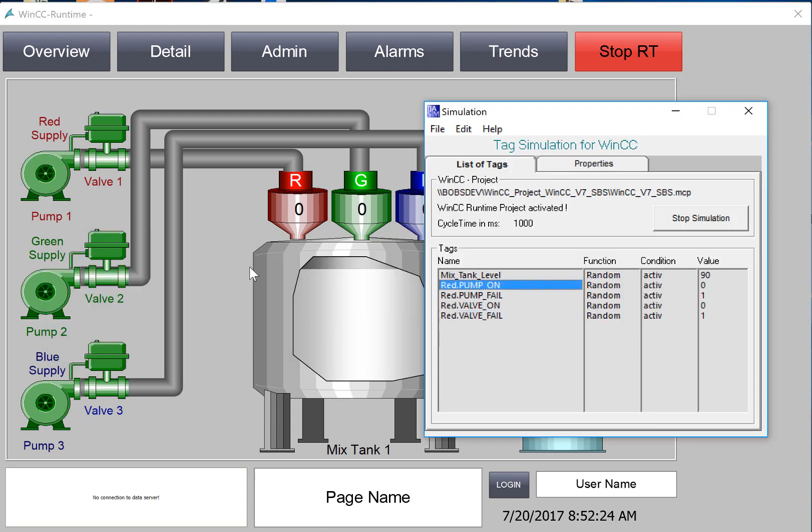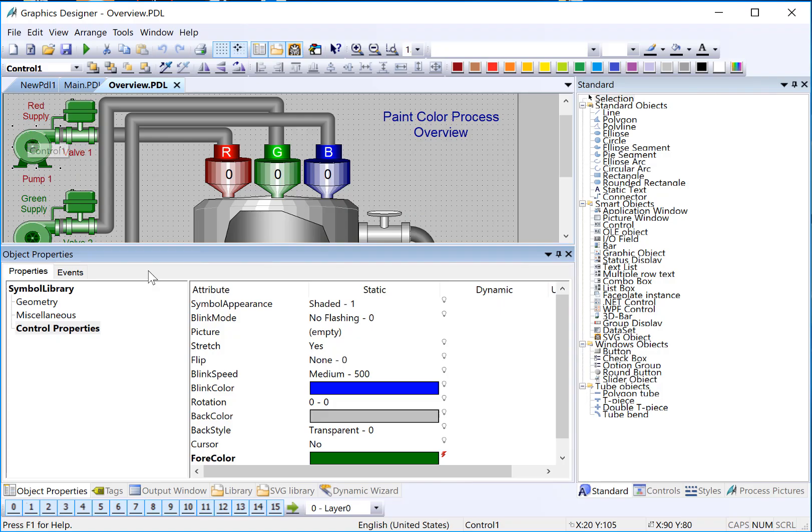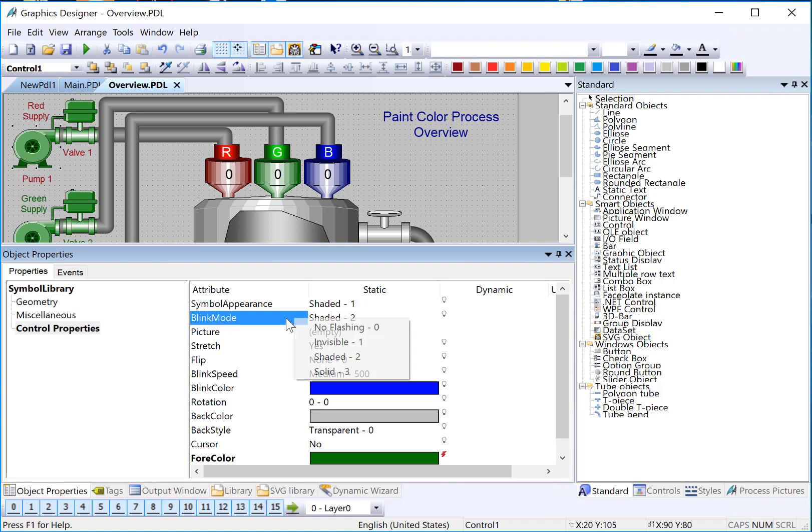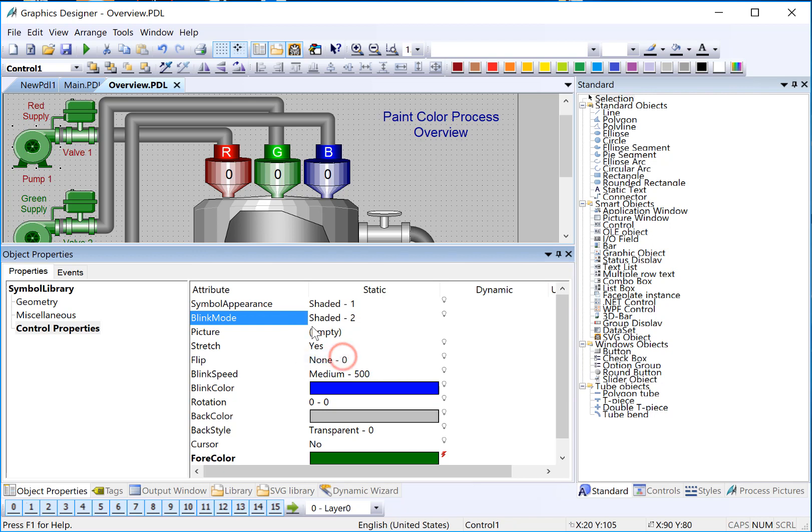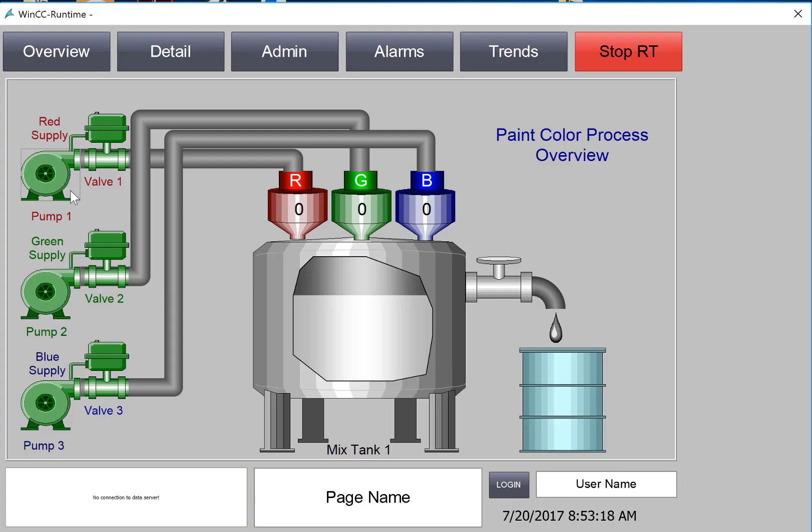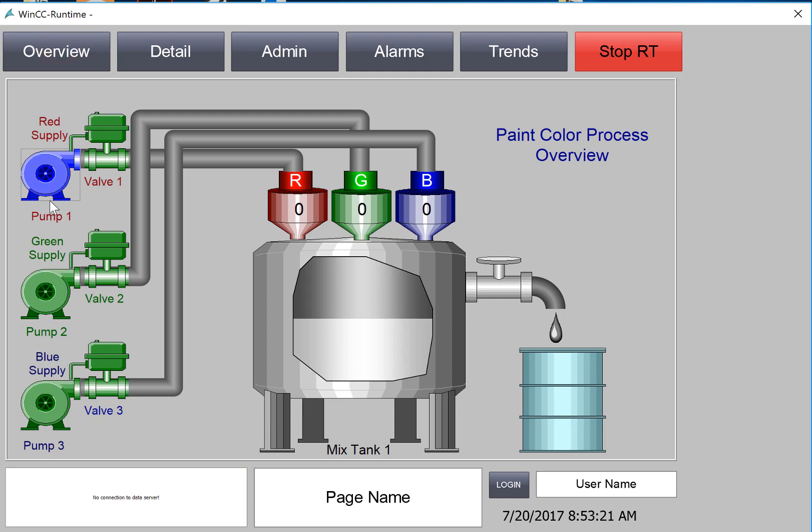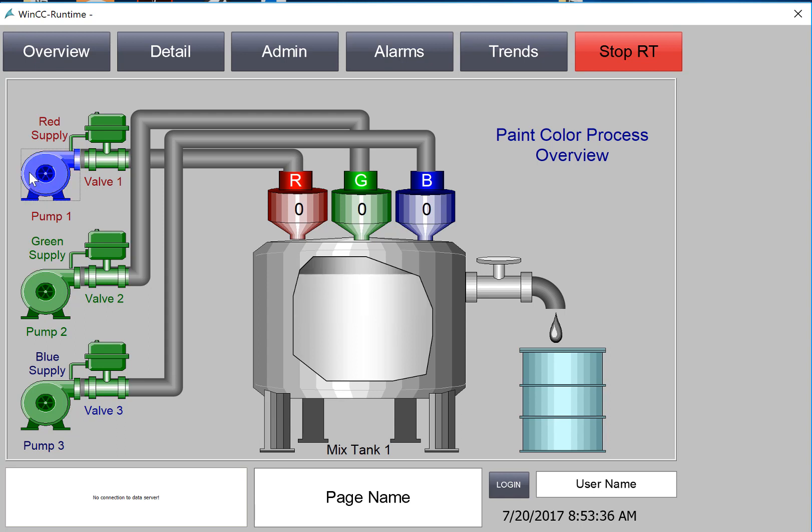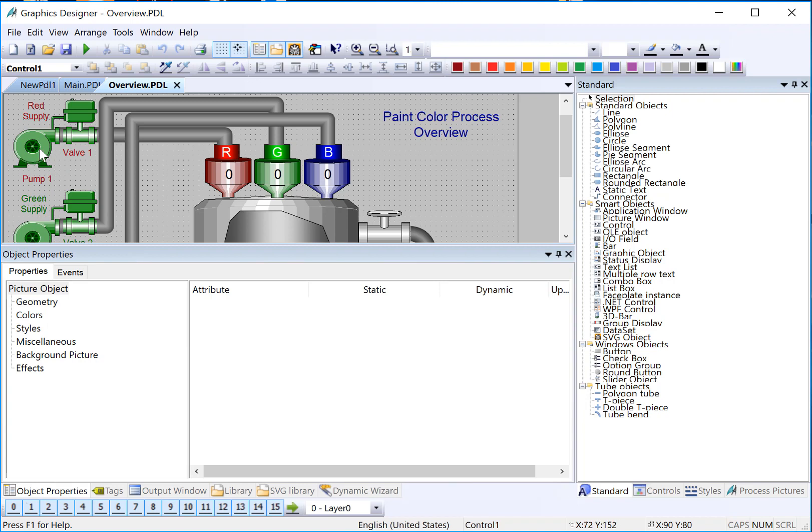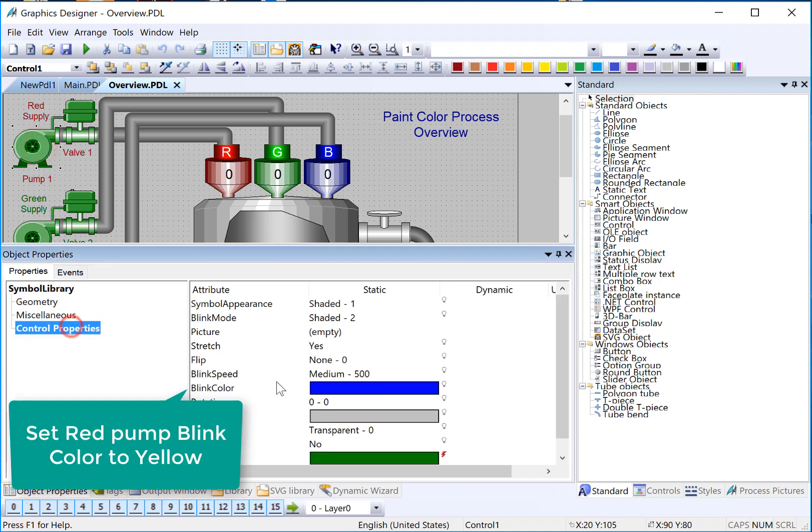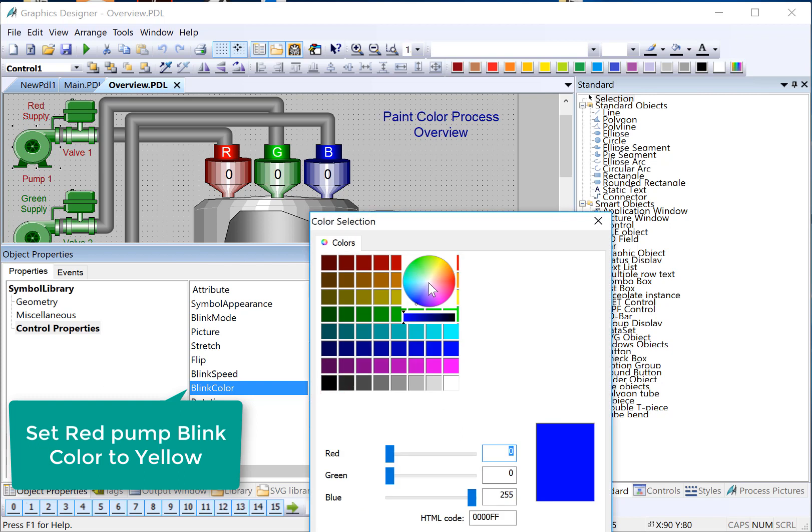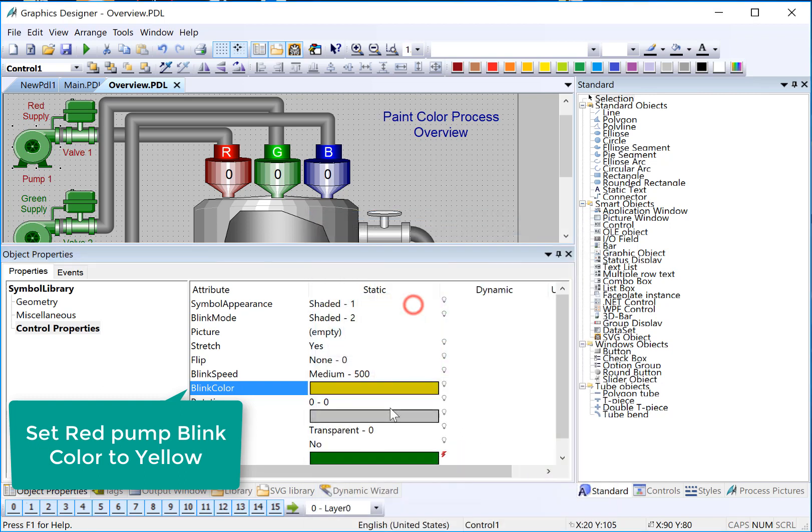So now, we're going to configure the fail color, where we're going to make the pump flash yellow. And then we'll do the same thing for our valve. We'll go back to the pump, and looking at the properties, if we look at our blink mode, we're going to use shaded. So just to show you what that looks like, I'll just set it by default to shaded. And then there's a blink color. Right now, it's set to blue. So if I save this, here's our runtime window, I have to refresh the page. But see how it's, when fail is on, it's blinking between blue and whatever color the pump is. So what we want to do is only if the fail bit turns on, we want it to blink, and we want it to blink, the blink color to be yellow. So the way we do this is first, we're just going to set our blink color to yellow. So I'll double click this and just choose yellow.